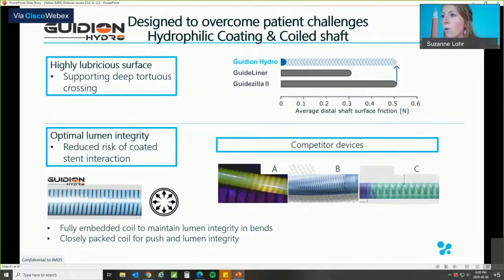The Guidion Hydro is also designed to overcome patient challenges, and therefore the hydrophilic coating and coiling design of the shaft are very important. In order to have a guide extension that can support deep tortuous crossing, it is important that the surface of the distal shaft is very lubricious. Therefore, we implemented a hydrophilic coating on the Guidion Hydro. We did testing, as you can see in the graph on the top, where we tested the friction over the surface of the distal shaft. As you can see, the Guidion Hydro has lower surface friction compared to a Guideliner or a Guidezilla. You can imagine that friction is something that you don't want for a guide extension. The lower the friction, the more lubricious the shaft is, and the easier it can cross in tortuous vessels.